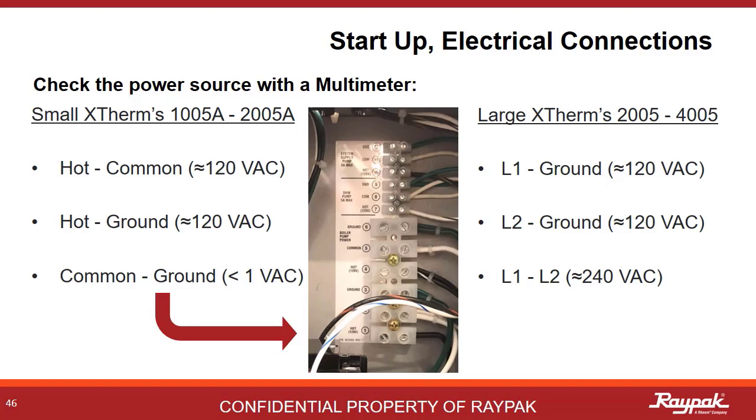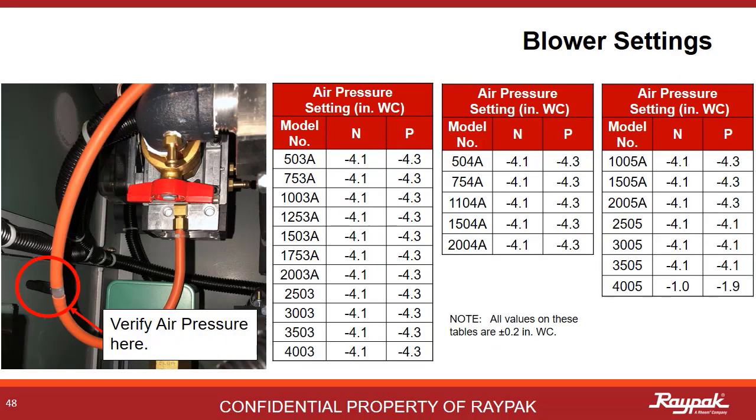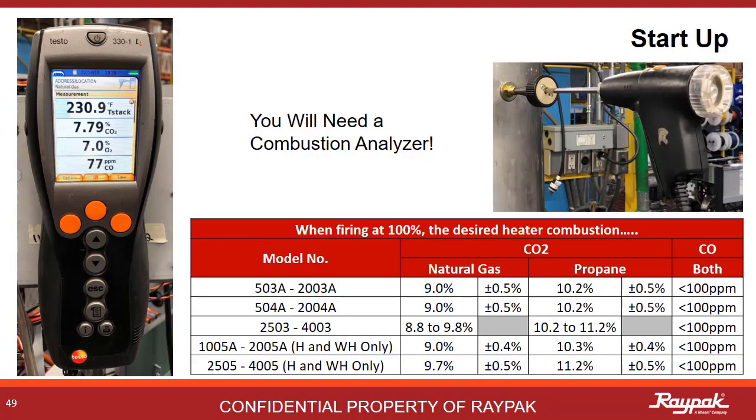Once all of the utilities are connected, it's time to start it up. The startup sequence is shown here. The first startup on a new heater might take a few tries to work all of the air out of the gas line. With the boiler fired up at 100%, it's time to check the air pressure. There is a T port on the silicone hose that runs from the gas valve to the swirler — be careful not to lose that black cap. It is very important to dial in the air and gas pressure settings before you use the combustion analyzer. If the air and gas pressure settings are way off, you may be producing too much CO and you can damage your combustion analyzer tool with a big hit from too much carbon monoxide.